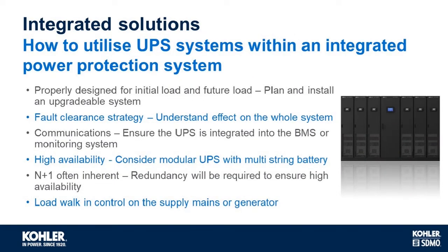Yeah, thanks Ian. As you were saying, it's very important that we look at the whole solution with the generators and the load. And in a lot of cases, the UPS is a very large part of the load. So we're just going to have a quick look through how we utilize the UPS inside that system, and how we make sure that we're using the advantages of the modern generators. So when we're putting the UPS in, we have to make sure that we consider what the initial load is and future load, and that makes sure we plan and install that upgradable system, understanding the types of load and where we're going to be when it's fully loaded.